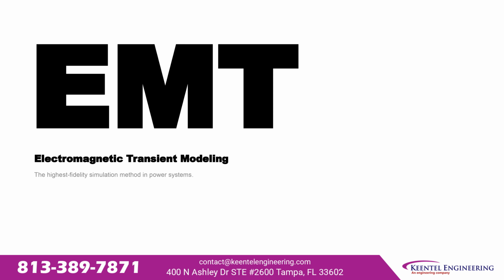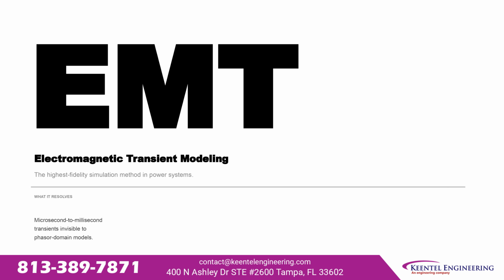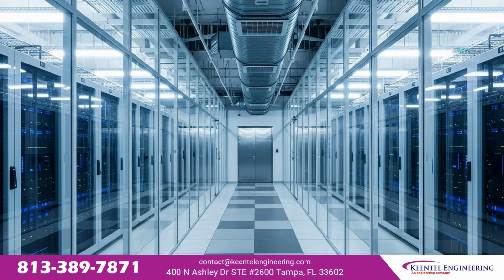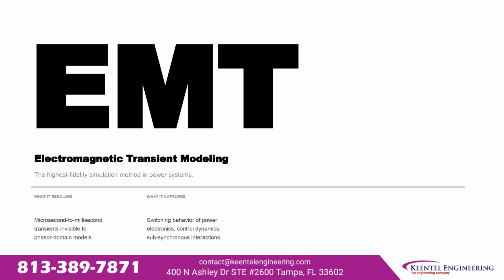Let's get into it. EMT, electromagnetic transient modeling, is the highest fidelity simulation method in power systems. What it resolves: microsecond to millisecond transients that are completely invisible to phasor domain models. What it captures: switching behavior of power electronics, control dynamics, and sub-synchronous interactions. The difference from RMS: RMS gives you average behavior. EMT gives you full waveform detail.